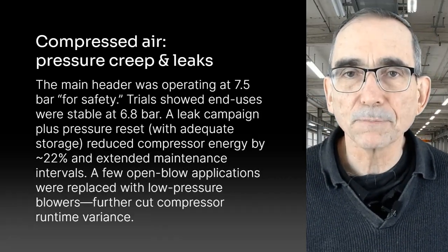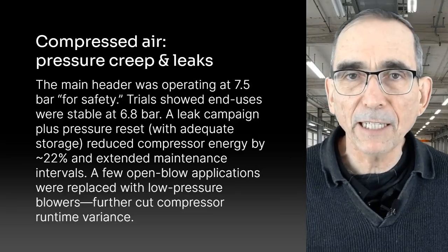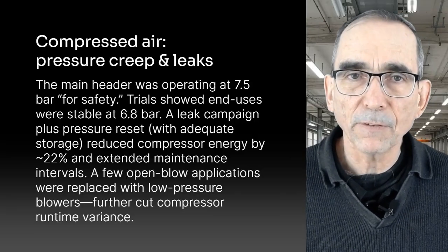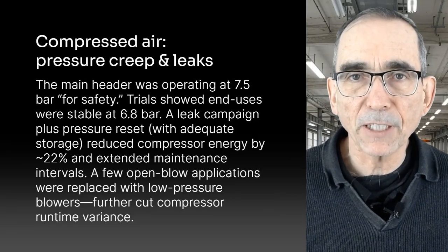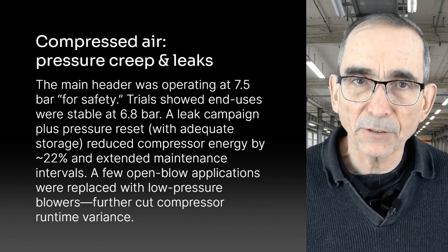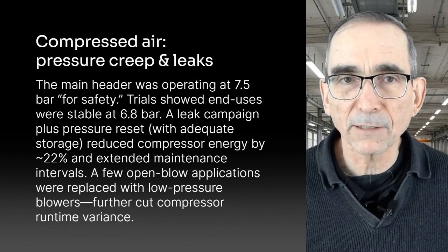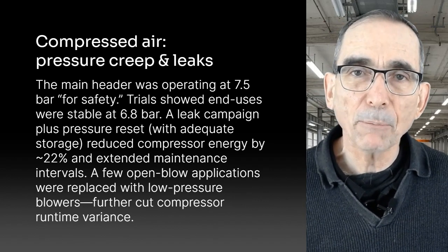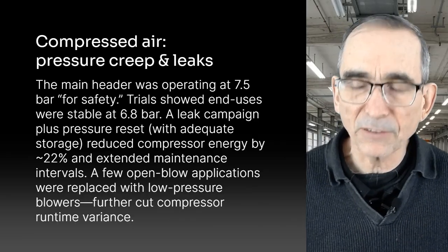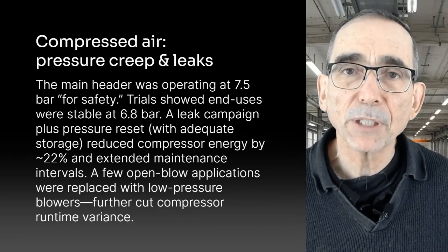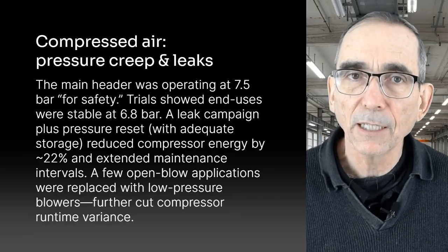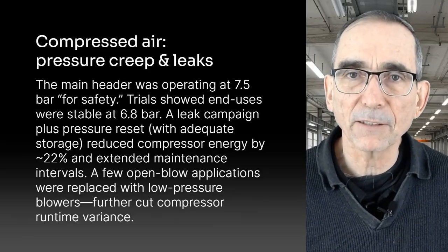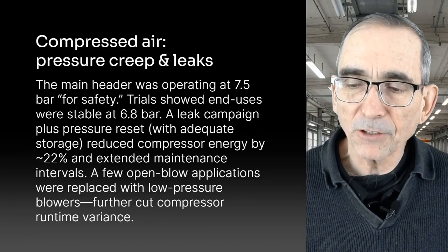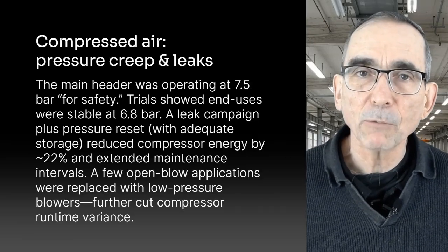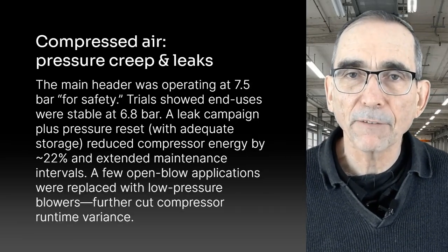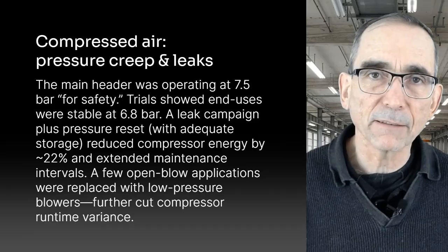Let's look at a compressed air example. A common one is that the pressure is a bit too high. The main header was set at 7.5 bar for safety, or 750 kPa. Trials showed end users were stable at 6.8 bar or 680 kPa. So a leak campaign plus pressure reset and adjusting the storage, again not necessarily a cheap project, but it did reduce compressed air energy use by about 22% and extended the maintenance intervals, reducing maintenance costs. Furthermore, a few applications where compressed air was just used for blowdown were replaced with low pressure blowers, and that further cut compressor runtime variance.